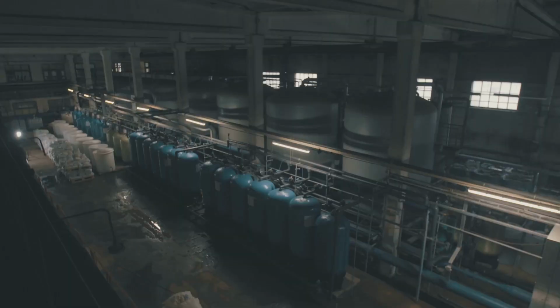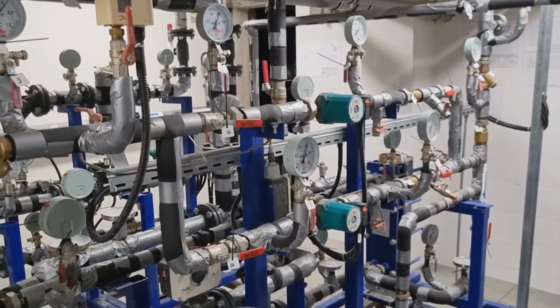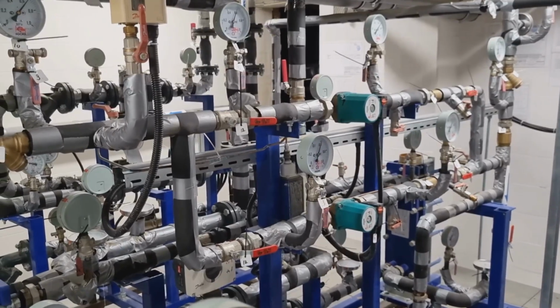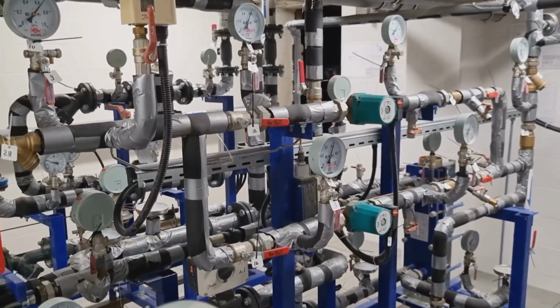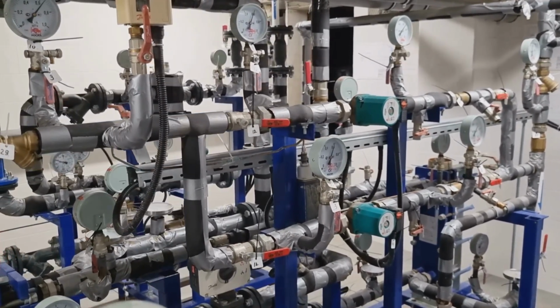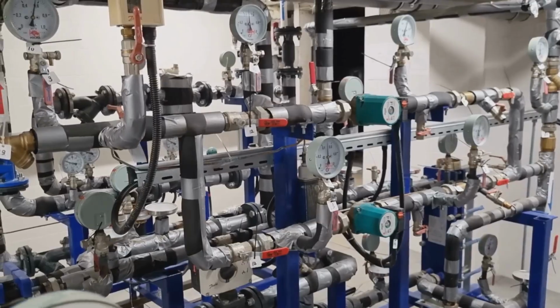One common setup is chilled water cooling. In a chilled water system, water is cooled by mechanical equipment and circulated through the building. That chilled water helps cool the air going into server rooms. As the water absorbs heat, it warms up. Then it returns to the cooling system to be chilled again. This creates a loop that moves heat from one place to another.